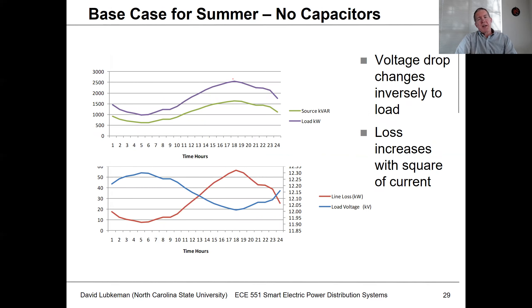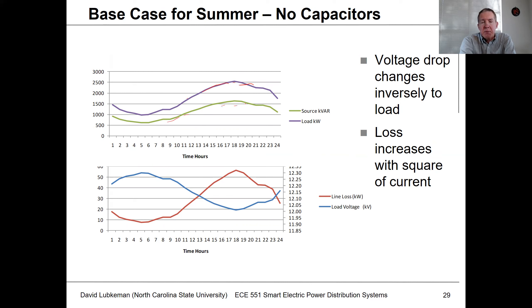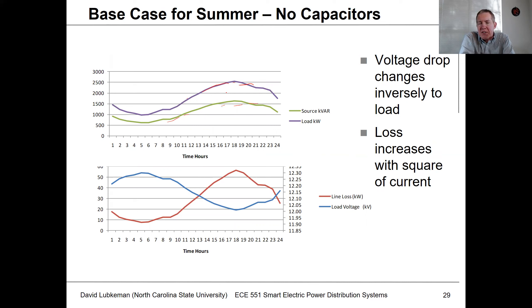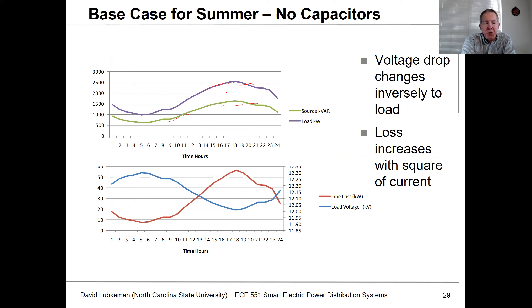Let's look at a base case with a summer profile. The top curve is real power consumption changing with time, and the green curve below is reactive power, assuming a constant power load. Basically, kVAR load is linked to load kilowatts as a function of time. For a sample circuit, if you look at the voltage at the load as a function of time, you get a curve where at light loading conditions the voltage actually comes up, but as load increases, the voltage drops until it's at minimum value during the load peak.